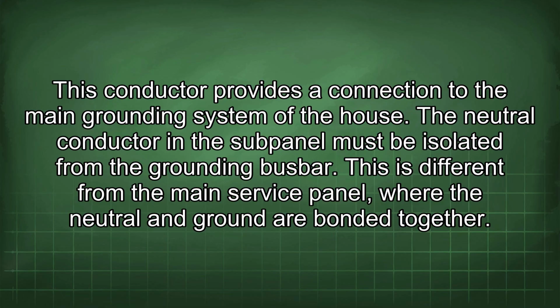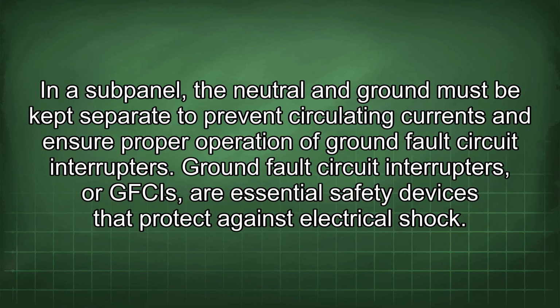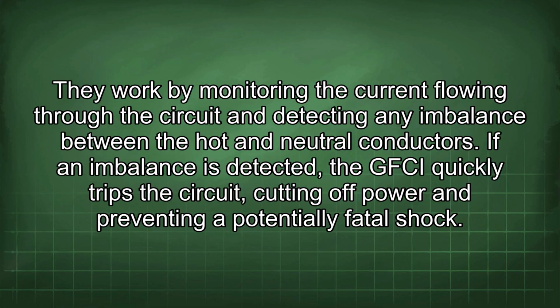The neutral conductor in the subpanel must be isolated from the grounding busbar. This is different from the main service panel, where the neutral and ground are bonded together. In a subpanel, the neutral and ground must be kept separate to prevent circulating currents and ensure proper operation of ground fault circuit interrupters. Ground fault circuit interrupters, or GFCIs, are essential safety devices that protect against electrical shock. They work by monitoring the current flowing through the circuit and detecting any imbalance between the hot and neutral conductors. If an imbalance is detected, the GFCI quickly trips the circuit, cutting off power and preventing a potentially fatal shock.